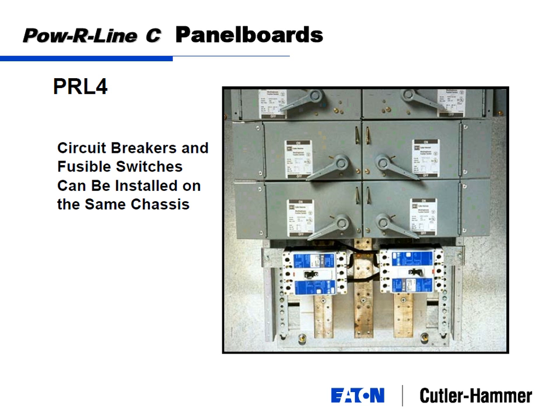Real estate guys, developers, everything's associated to the cost per square foot. If I've got a building with a cost of $400 per square foot, that means if I have to take up 2 extra sections of panel board because I'm using fuses instead of a breaker, I'm costing myself 400 times 2 feet here by 6 feet there. You can do the math and figure out there's a cost associated, not just in material, but in the cost of using available footage for an extra panel board section.